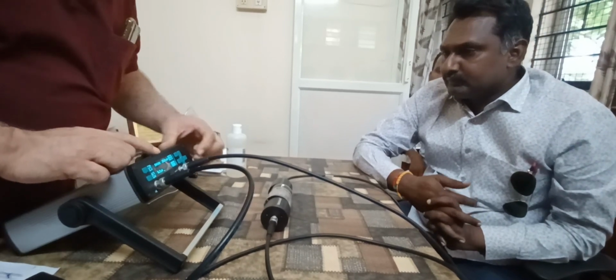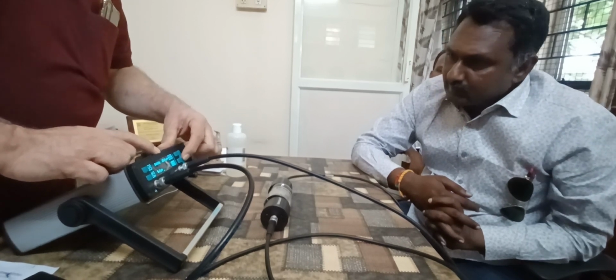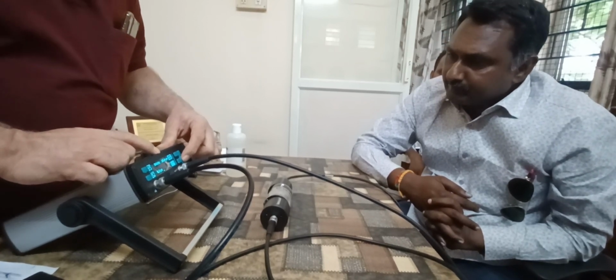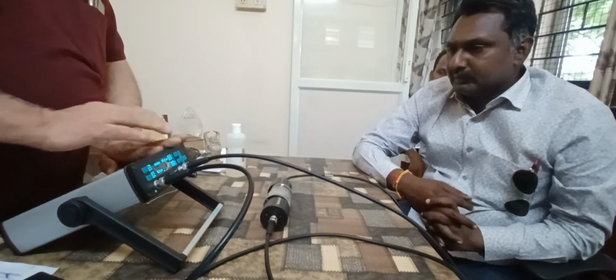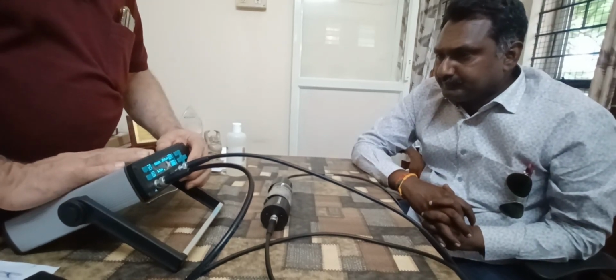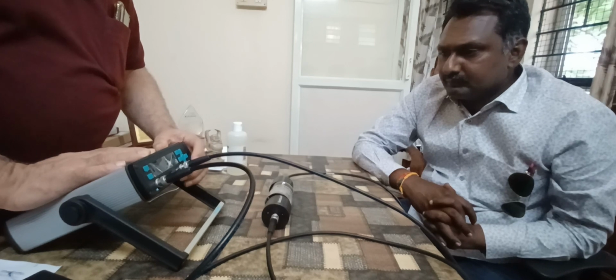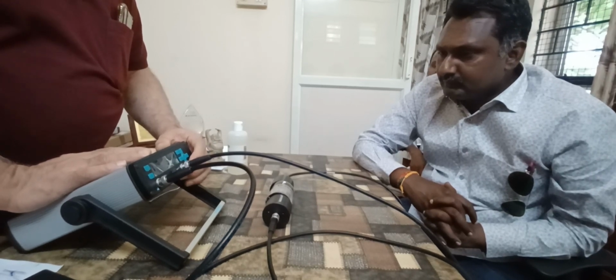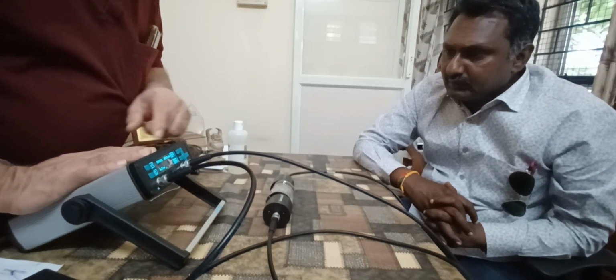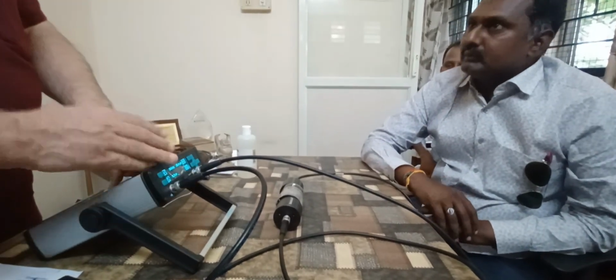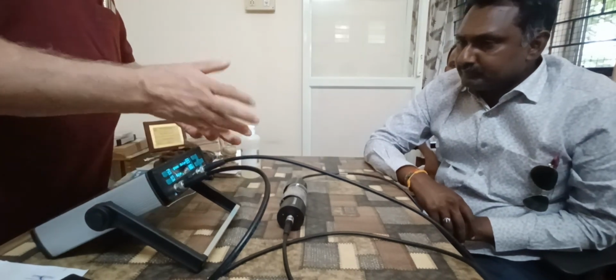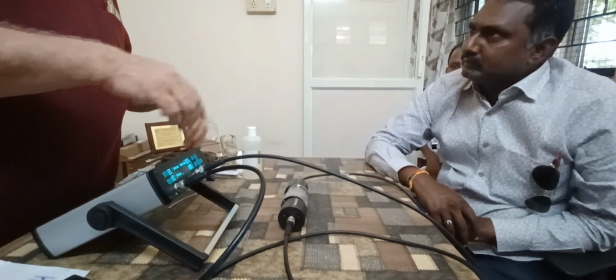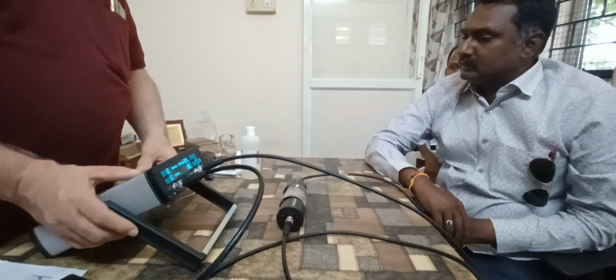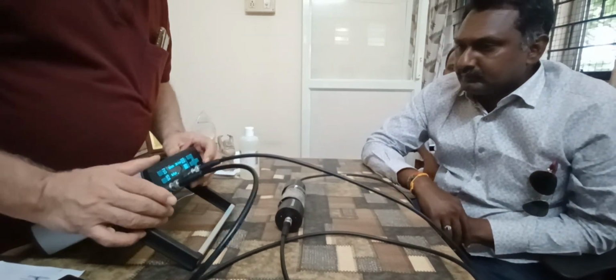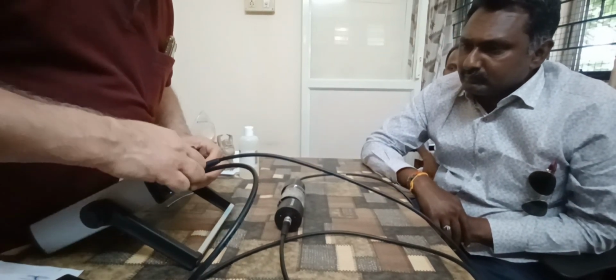Now the setting has changed. This center button is the saving button. Save it once, so that when you switch it off and switch it on again, these settings will remain. Otherwise, whatever earlier setting was there will come back. If you have not noticed it and go and test, it will not give you an accurate result. Okay. And now there is one down arrow here.